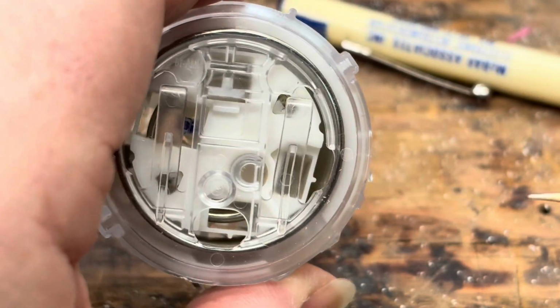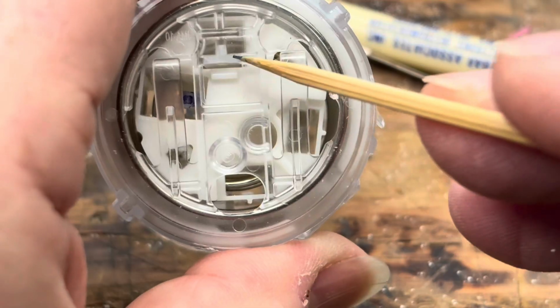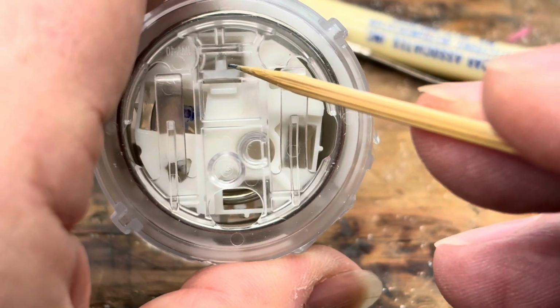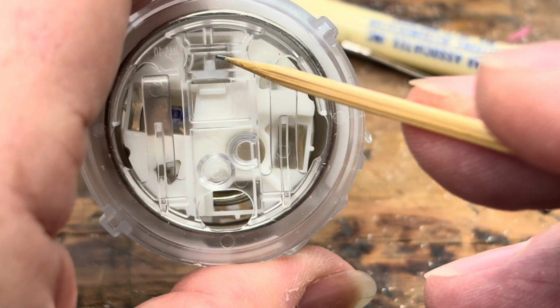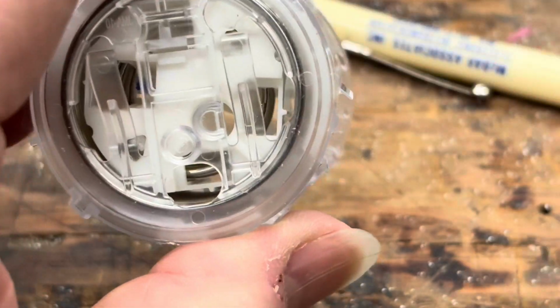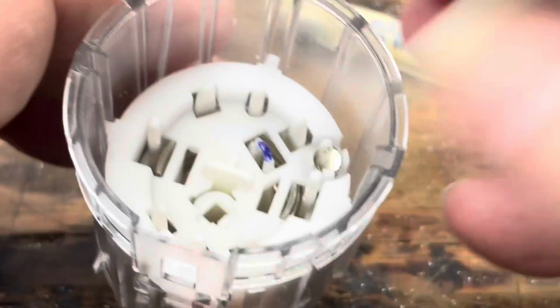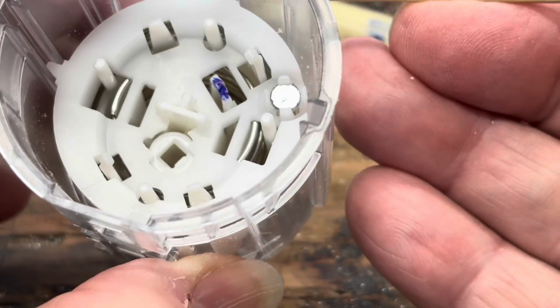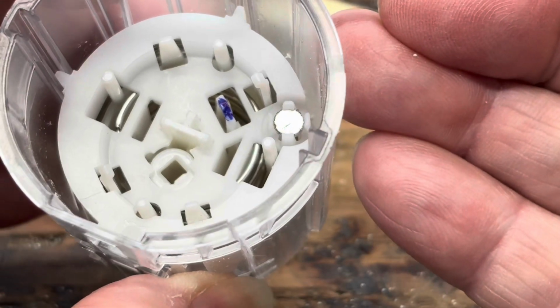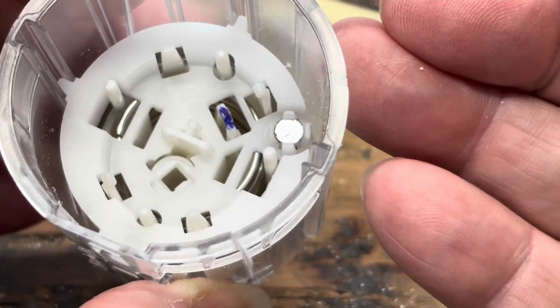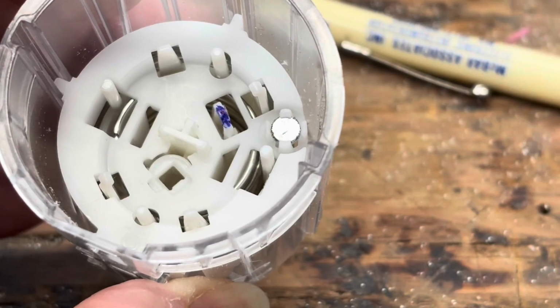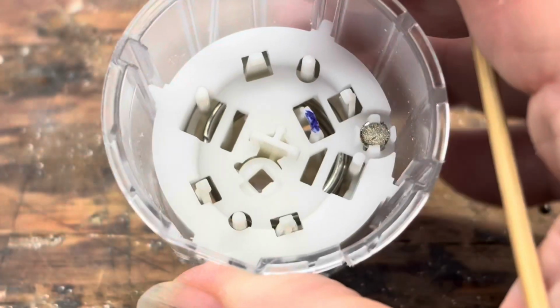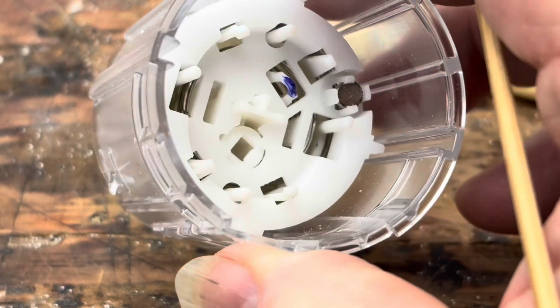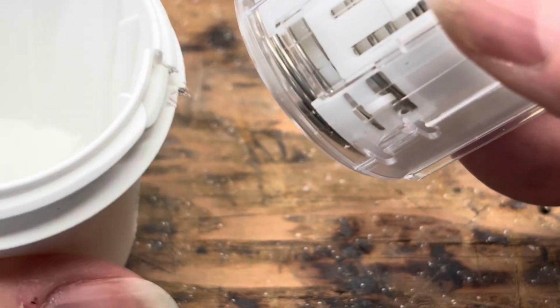And you can't see it very well, but right here is that arm in cup 2 that passes through cup 3, ready to hook that ledge on cup 4 when this 3-4 unit travels far enough. The hook on cup 2 arrests cup 4, releasing the spring between 3 and 4, so the needle retracts after it's inserted the probe in the user's arm.